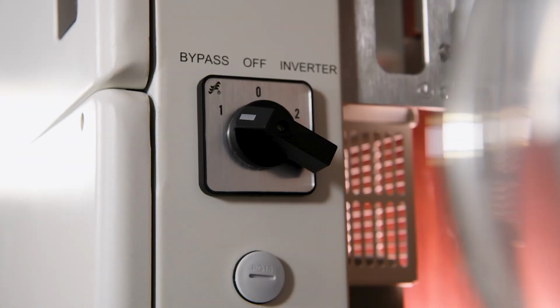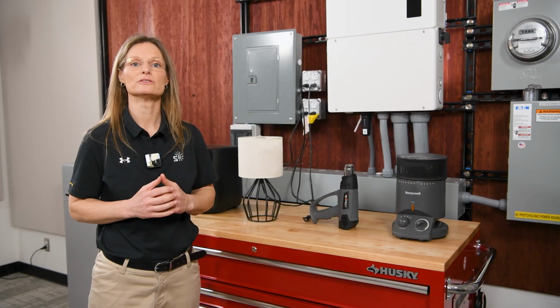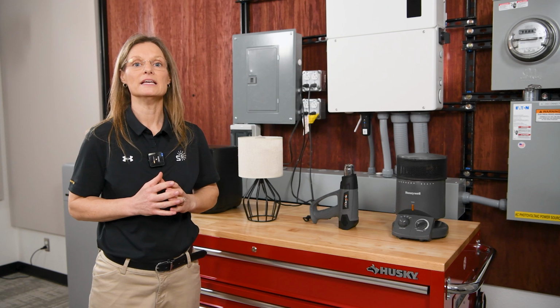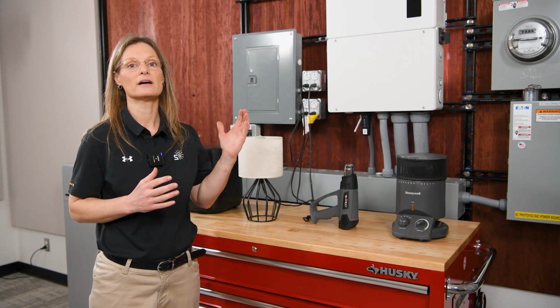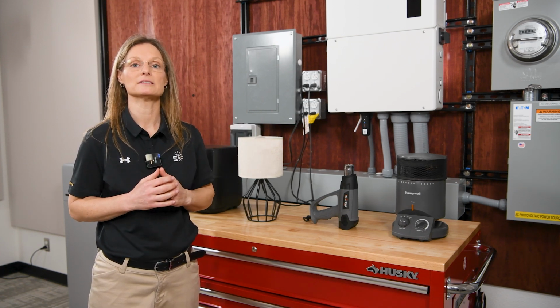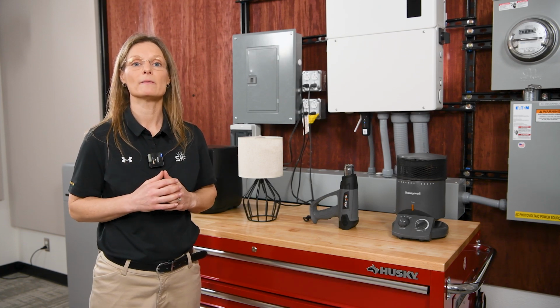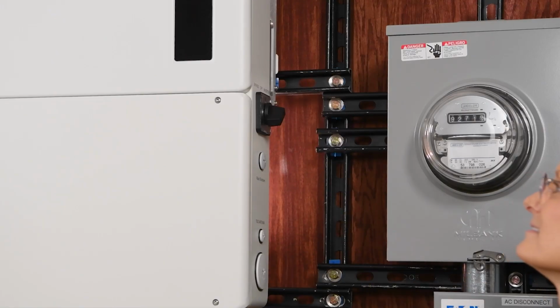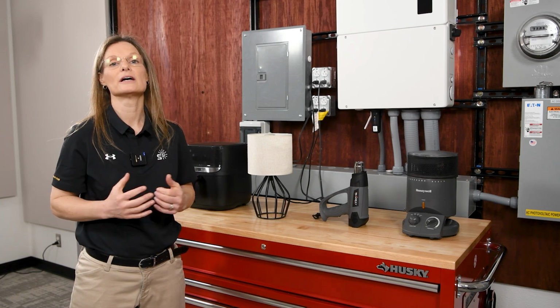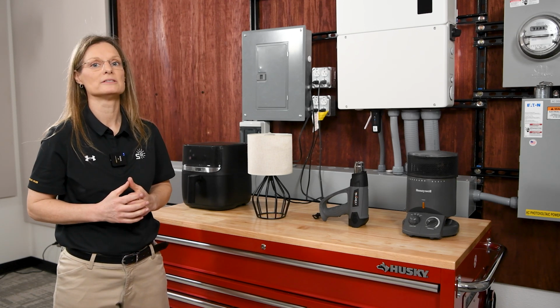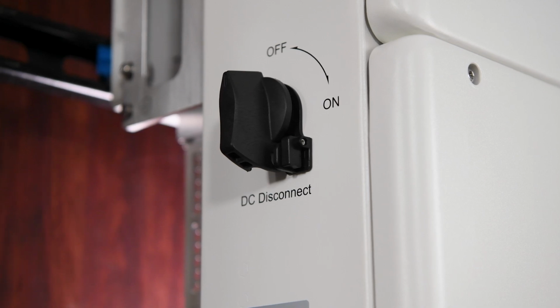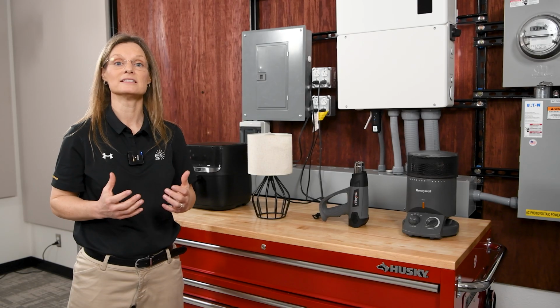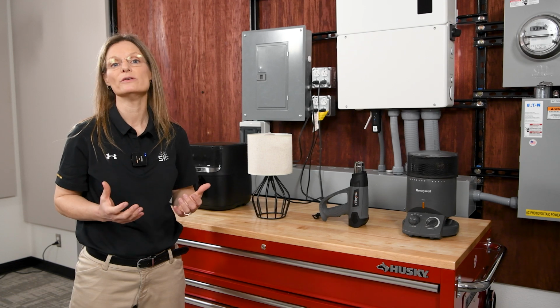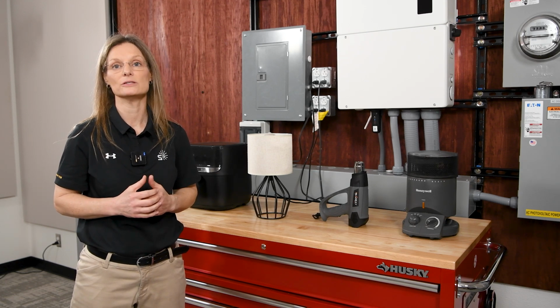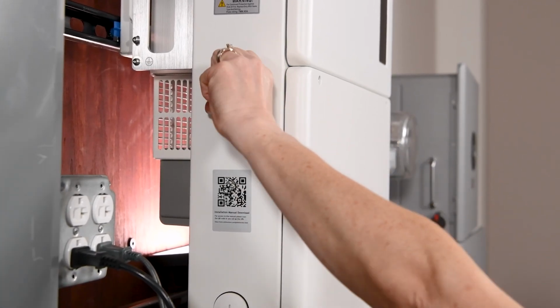Our bypass switch has two settings. In the event we want to operate as backup power, we need to make sure our switch is set to inverter. If we're having problems with our equipment, we need to switch it to bypass. Since we're operating in backup power, we need to switch ours to inverter, so we'll go ahead and do that now. Then we need to turn our inverter on by turning the PV disconnect switch to the on position - this is like the on button for your inverter, whether you have PV or battery connected or not. We'll go ahead and turn that on now.